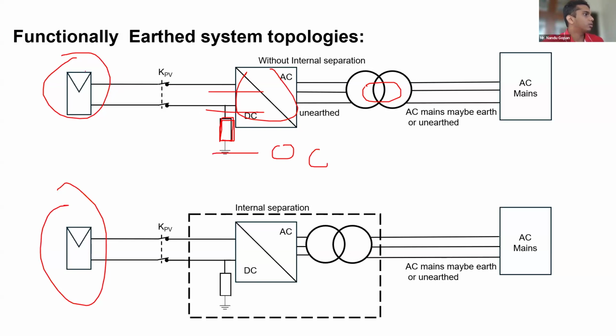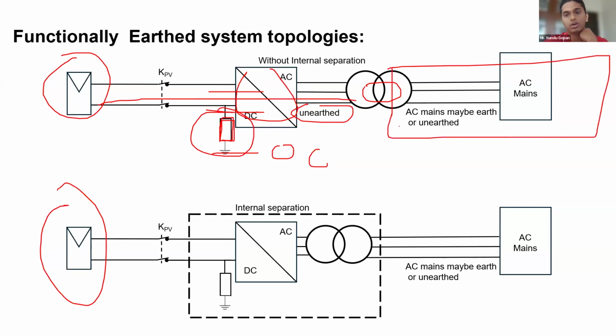I will be explaining this in a little more detail. This separation can be internal to the inverter, or you are supposed to provide a separation outside the inverter also. Both of these come under functionally earthed system topology. In a functionally earthed system topology, the earthing of the conductor will be done at only one point on the DC side, and the other side will be unearthed. On the AC mains side, it depends. You can have it earthed or unearthed. It depends on the supplier or the consumer.